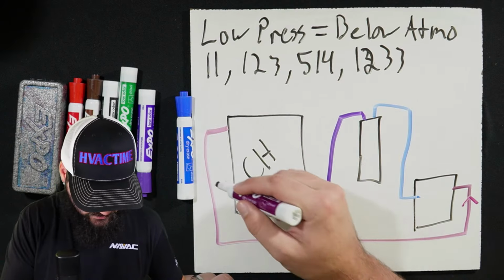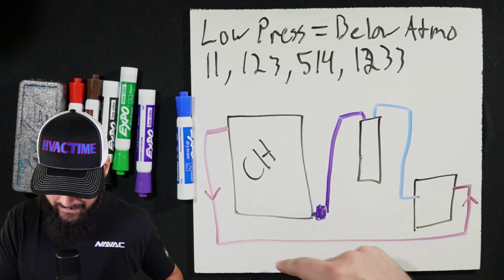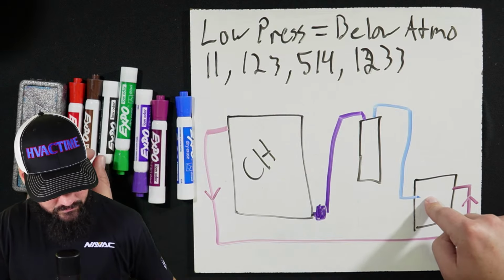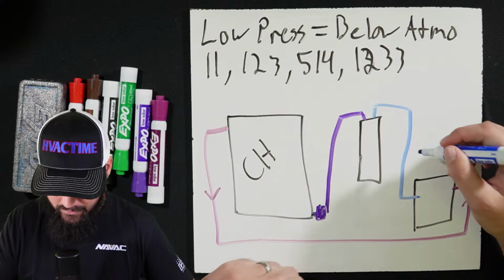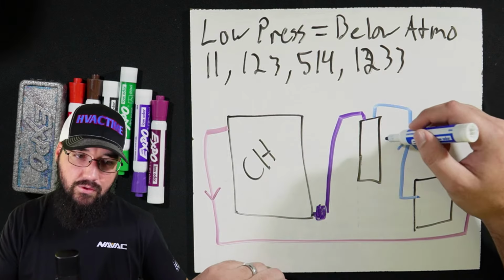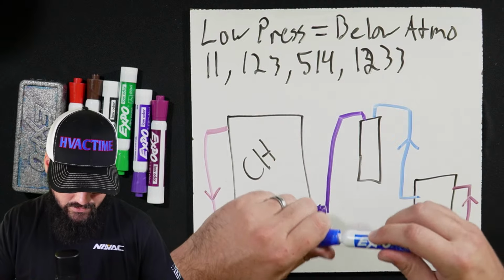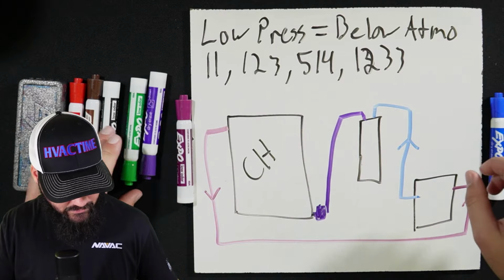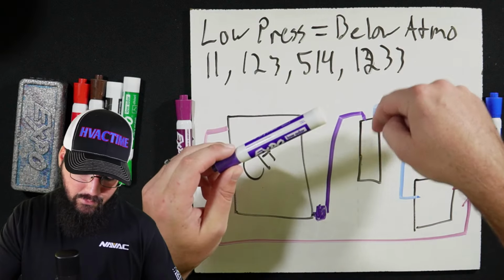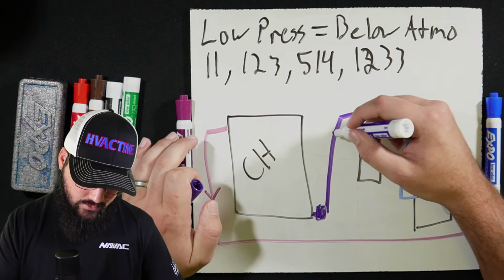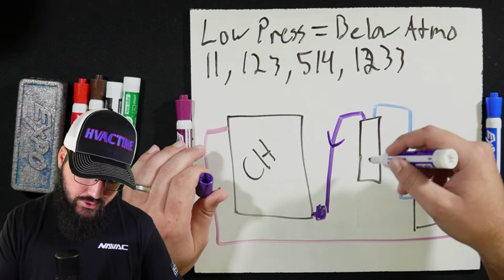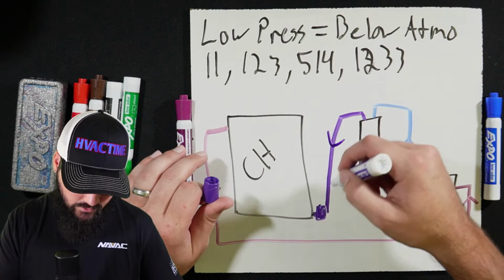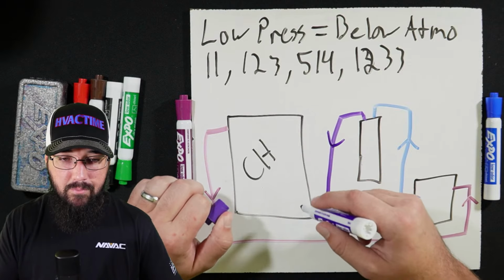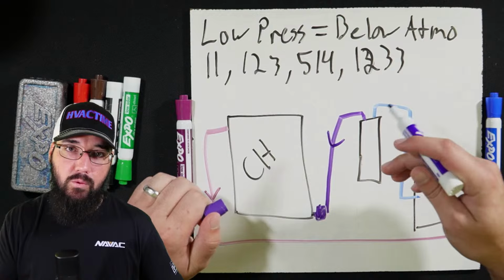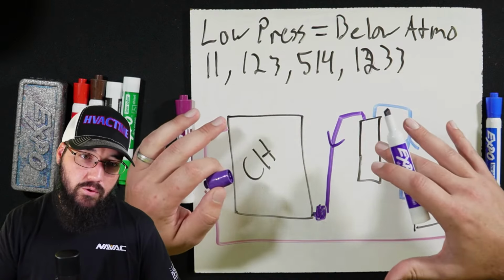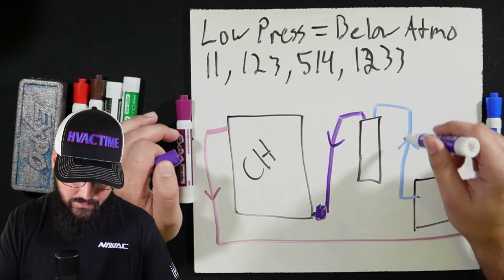Okay, so we're going to flow this way. We're going to be drawing into the recovery machine. And we're going to push that vapor out of the recovery machine and into our recovery cylinder. That recovery cylinder is then going to allow that vapor to push in on the vapor port and draw out, or push out, I should say, into the liquid charging port of the chiller. Now we may have multiple tanks, we may just have one really big large tank that's able to hold the whole charge. Either way, this is the basic flow.